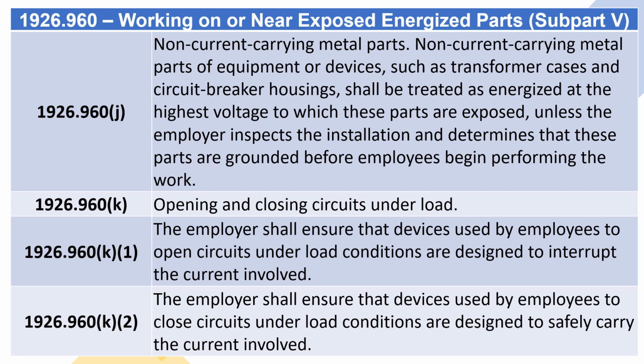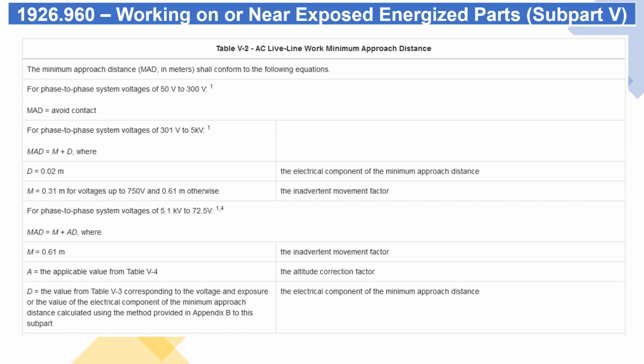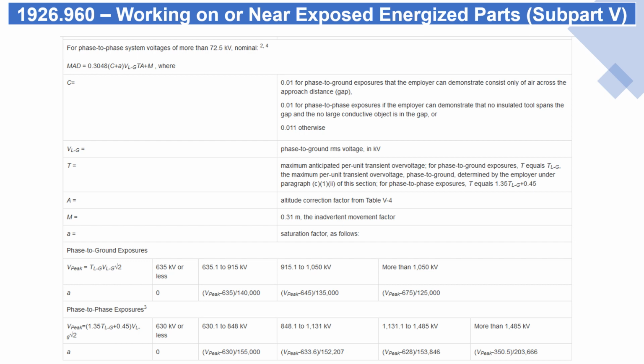1926.960 K. Opening and closing circuits under load. 1926.960 K1. The employer shall ensure that devices used by employees to open circuits under load conditions are designed to interrupt the current involved. 1926.960 K2. The employer shall ensure that devices used by employees to close circuits under load conditions are designed to safely carry the current involved. Table V2, AC live-line work minimum approach distance.